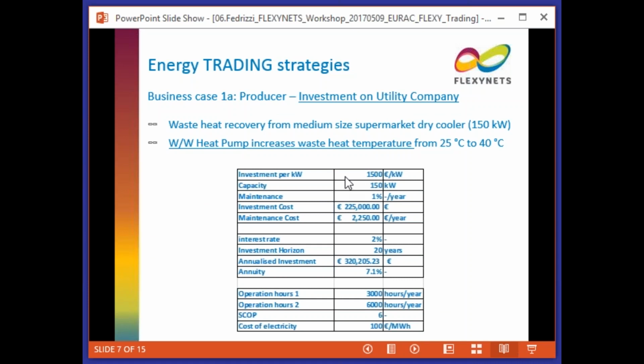So here we look into the situation where we have a medium-sized supermarket with a refrigeration cycle that wastes 150 kilowatts into the environment. The idea here would be to have a substation, including a heat pump, connected directly in parallel to the dry coolers of the refrigeration cycle and raising the temperature from 25 to 40 degrees. And then this 40 degrees thermal energy is fed into the grid.